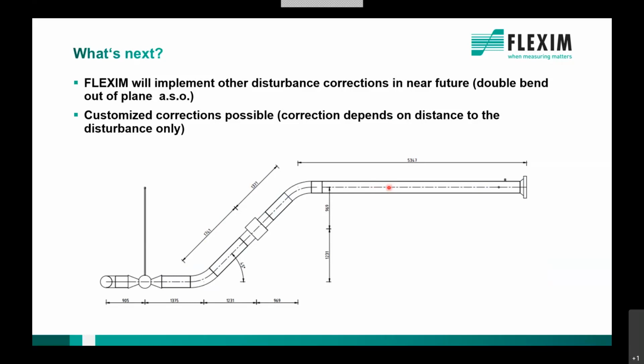That means it can be used on any piping which looks basically the same, which is the same inlet conditions. This correction factor works on all of his dosing stations. So that's what he basically does. And that's one output from the PTB test, that once you have a disturbance correction for a specific disturbance, you can use it on any pipe size, on any fluids, either gas or liquids, for any flow velocities, as long as you are in a turbulent flow regime. It applies for all of those at the same time.